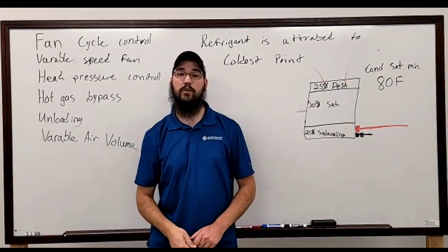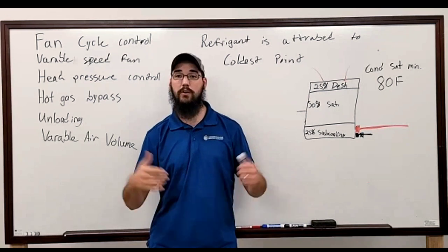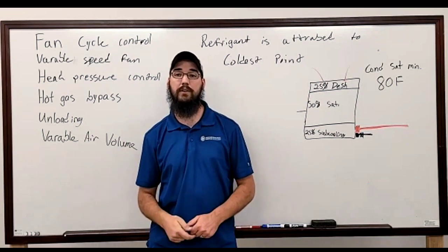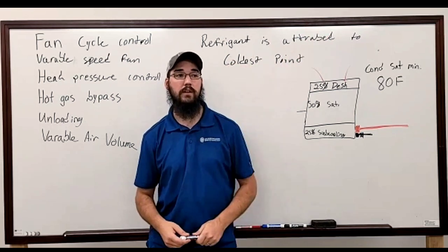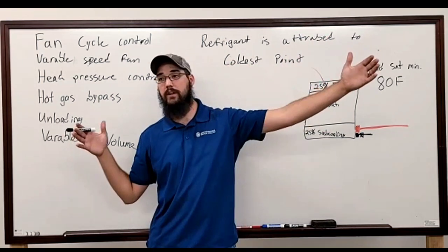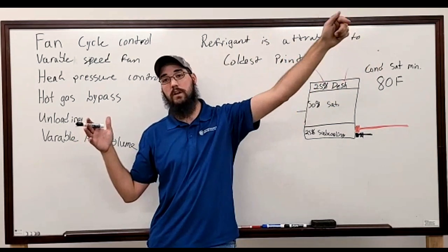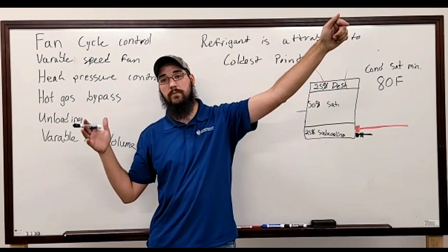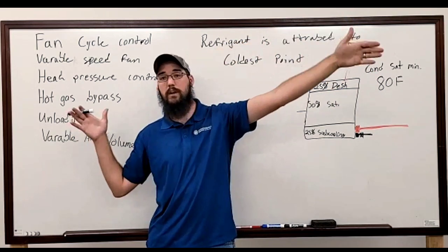There again, we've got our newer series of Trane air-cooled chillers coming out where all the fans are running off ECM motors, and they're on a comm bus between each fan. So you may have 24 fans on top of this one chiller, and every fan is interlinked through this bus. And we've had it before where one fan shorts out internally and it takes the whole bank down.